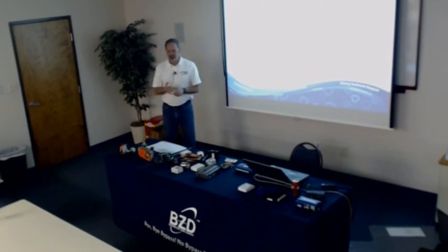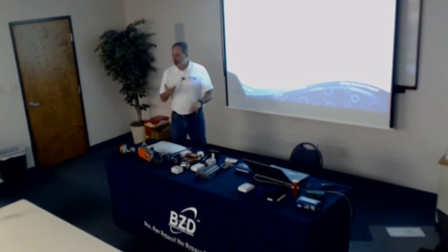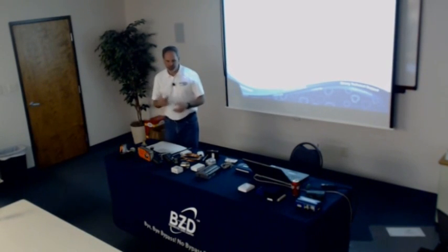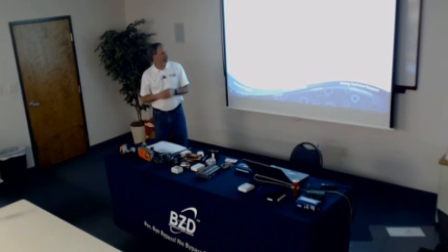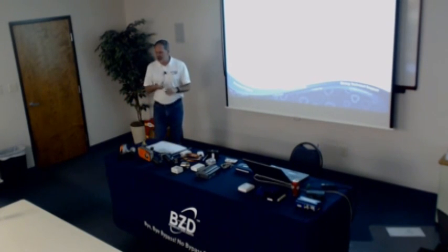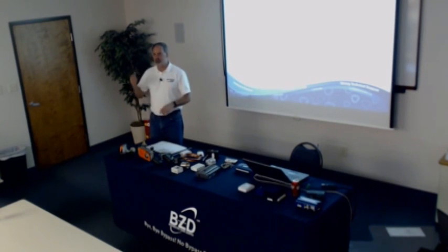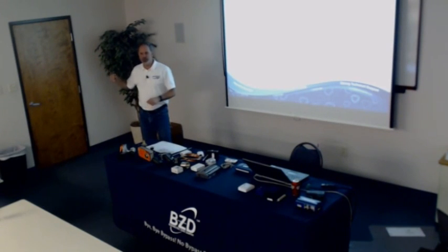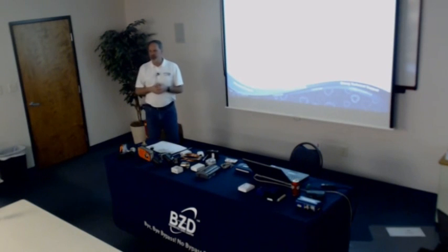This one happens to be a CO2 sensor for measuring CO2 in a room. Duct pressure transducer, just a pressure switch, and a current transducer. And finally, carbon monoxide transducer for like a parking garage. So as you can see, there's just about a sensor to read anything you can imagine. Temperature, dew point, enthalpy, or you could figure enthalpy based on a temperature and humidity sensor, put them together. The controller actually has a little block that will calculate that, do that math for you. Gas detection, the gas might be CO2, it might be refrigerant, it might be carbon monoxide, whatever the gas is, you can detect it. I didn't bring one in, but there's light detection, so that if you have a big atrium in a building and the sun's out, you can detect the light level in the room, either shut off or dim the lights in the room.